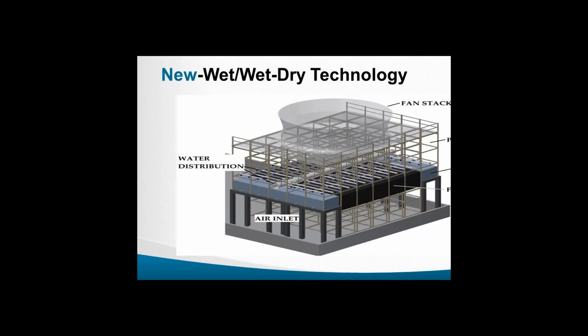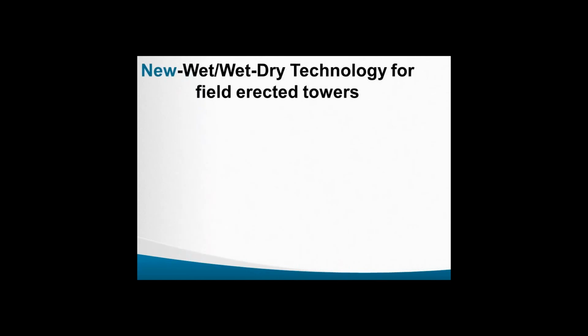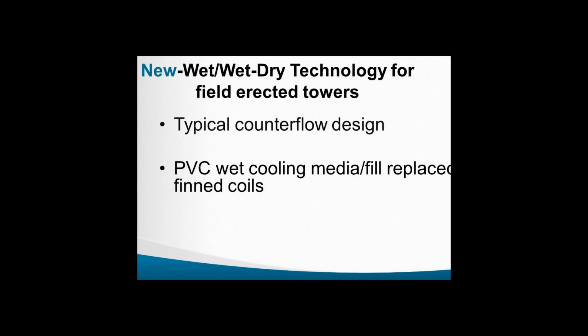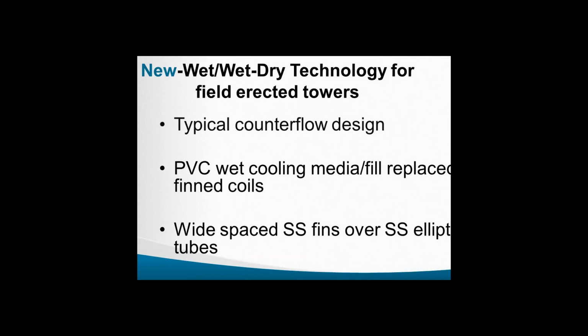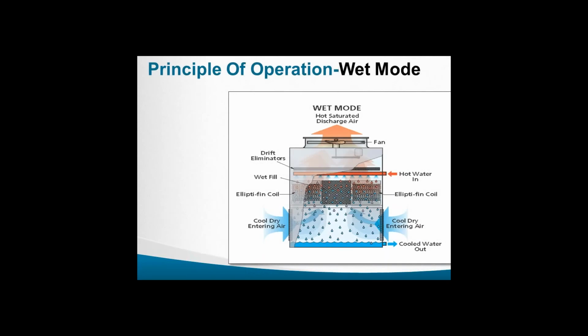The last hybrid design is in the field-erected power plant cooling tower size, and it's a combination of having heat transfer or fill pack in the middle, and on the outside of the tower you have stainless steel fin tubes. And so you can run the water either through the fill pack, through the fin tubes, or a combination of both. They're stainless steel, so you can drain them down, and you don't have to worry about corrosion. If it was a galvanized steel coil, you'd have issues draining the coils out, and they would rust. So you typically would see this in a counterflow design, PVC fill. Some of it would be replaced with a stainless steel tube with fins. So in this design, the hot water comes in the header and sprays over the coils, and it sprays over the fill pack. And the coils actually act as kind of like a fill heat transfer. Water runs over and is cooled off.